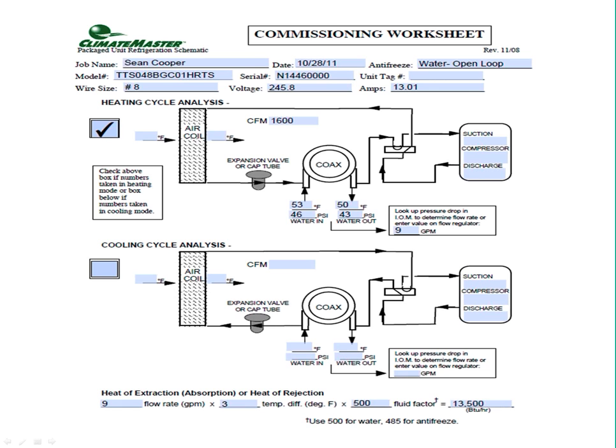Next, you're going to probe in, and it doesn't matter which order you do this, your pressure gauge. Again, it needs to be a large dial, 3.5-inch dial face, so you can see the movement in the needle. In this case, we're showing a 46 psi entering and exiting at 43. So we have a 3 psi pressure drop. When you go to the reference tables, again illustrated in the water side analysis video, you will find that that equals, on this particular TTS, which is a single speed, 048, 4-ton, about 9 gallons a minute.